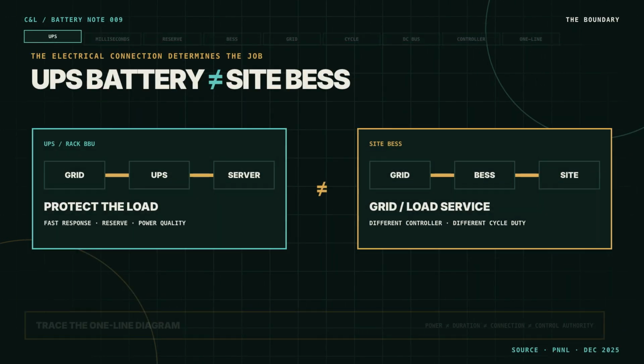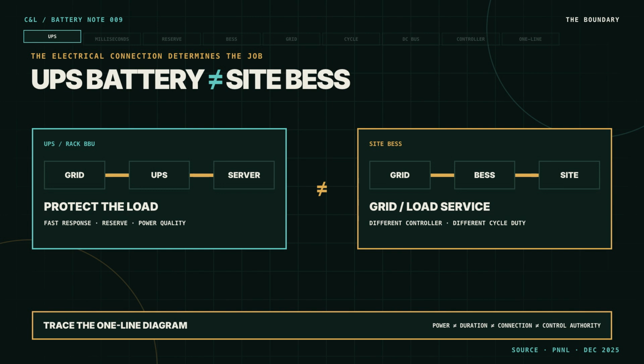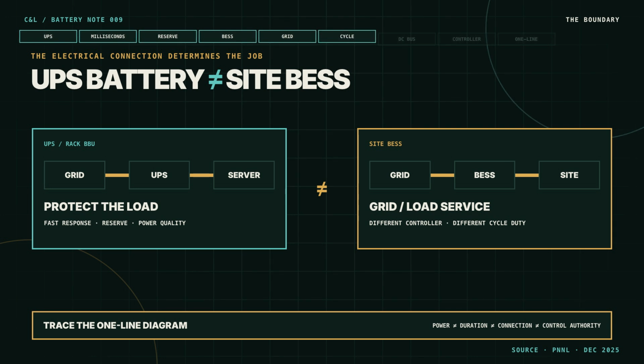Now separate two assets that headlines often merge. A UPS battery protects the computing load. Its priorities are immediate response, power quality, and guaranteed reserve. A site battery energy storage system may have a broader job: grid support, load shaping, renewable integration, or longer ride-through. Pacific Northwest researchers warn that existing UPS batteries are not automatically suitable for continuous smoothing. Cycling can consume useful life, and some grid disturbances may force the UPS rectifier offline to isolate the protected load. That can create a need for a separate utility-scale battery or power electronics device.